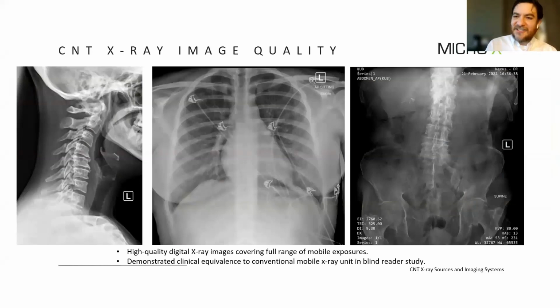The image quality is largely determined by the detector, the quality of the digital detector, and the software. We partner with a variety of detector suppliers, and for the Rover, we work with other people's imaging software rather than our own, and other people's detectors, but we integrate it into our system directly. So the system acts as a fully integrated system. There's a screen on the system to review the images and set up the exposures, but it works with a variety of detectors, Carestream, Varex, Fuji, and others, which are just a few of the detectors that we work with. We can really partner with anyone's digital imaging detector for this application.